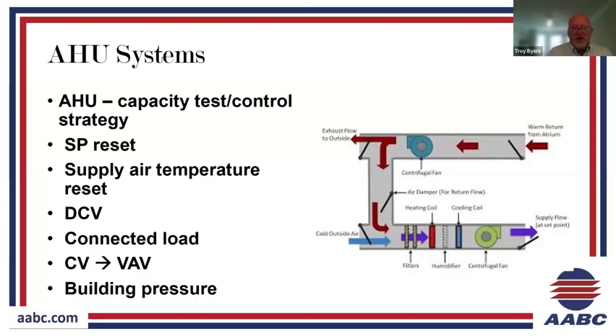Because A, we need to know a baseline, what we have, and then B, we need to know if we have any adjustment, if we need to try to go up or down based on current conditions. So we want to get a static pressure profile across that unit, meaning measure the pressure in each area of the air handler across any component, such as a fan or a filter or coil or dampers, to see what's going on, where the air handler is utilizing power to overcome resistance within the unit.